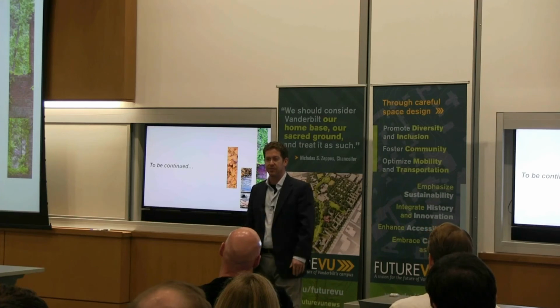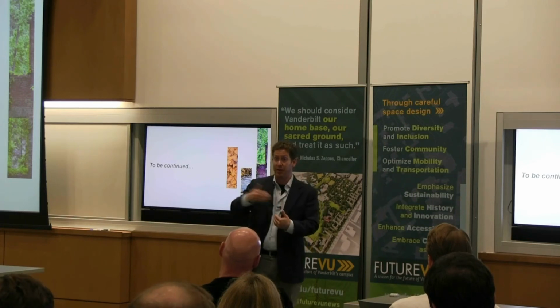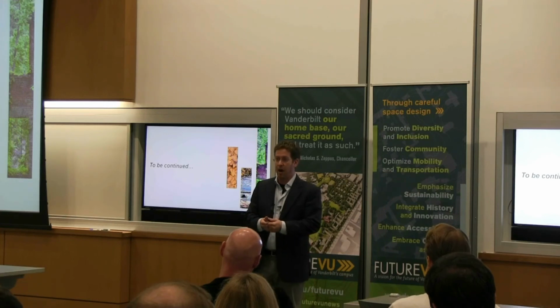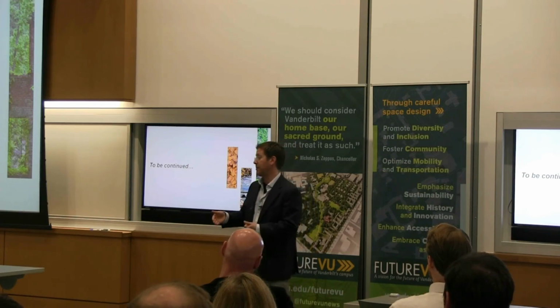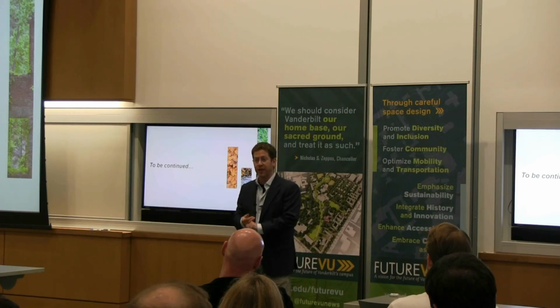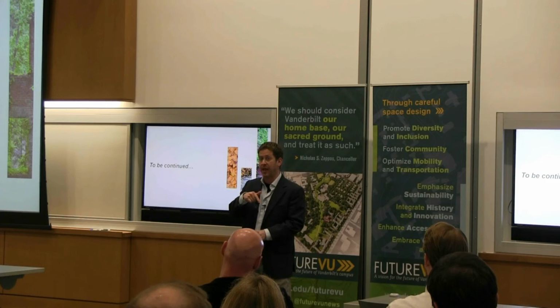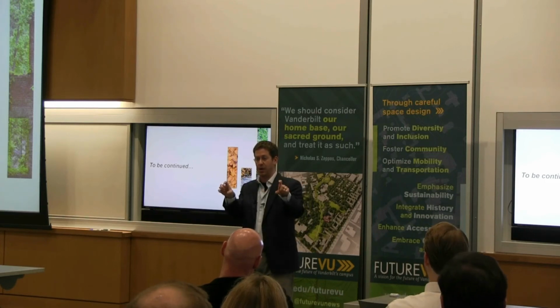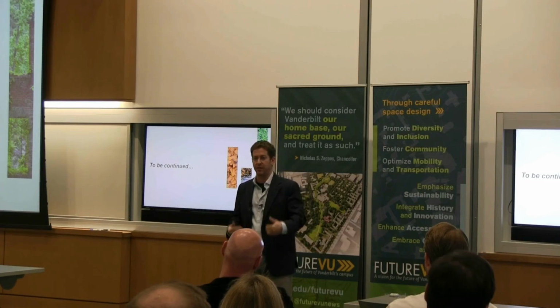And to dive off on a similar note, one of the things that the Living Building Challenge requires is operable windows, not every 30 feet, but you, as an occupant in regularly occupied spaces, you always have to be within 30 feet of fresh air. And so we had a lot of very long discussions about whether or not those windows should be manual or BMS controlled and the implications of that and what it really meant. And what we found was that both the Georgia Tech's mechanical engineers on staff and our mechanical engineering team were extremely concerned with someone leaving a window open on, say, a July day, maybe in the evening, maybe it's okay, and then it doesn't get closed. And our mechanical systems are operating in a very narrow band, as I was discussing before, and so the ability for the building to recover from that type of mistake could impact comfort in the building for quite a while. So we decided that we wanted all of that to be automated.